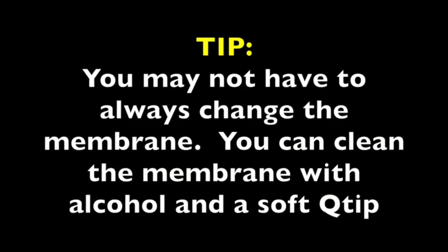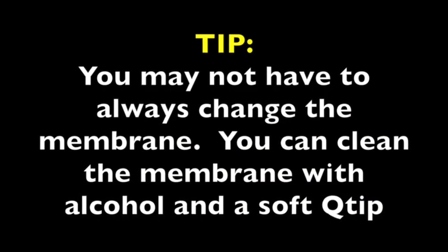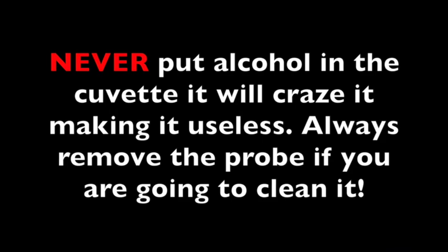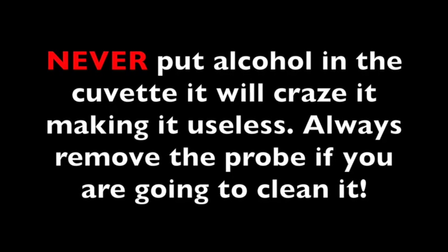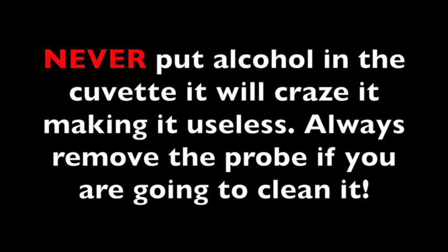You may not have to always change the membrane. You can clean the membrane with alcohol and a soft Q-tip. Never put alcohol in the cuvette. It will craze it, making it useless. Always remove the probe first.